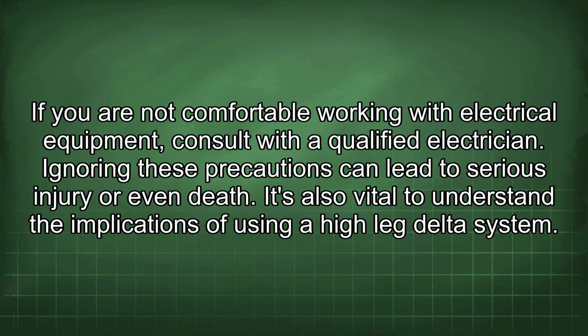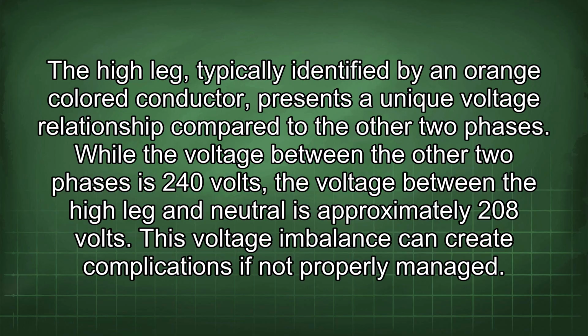It's also vital to understand the implications of using a high leg delta system. The high leg, typically identified by an orange-colored conductor, presents a unique voltage relationship compared to the other two phases. While the voltage between the other two phases is 240 volts, the voltage between the high leg and neutral is approximately 208 volts. This voltage imbalance can create complications if not properly managed.